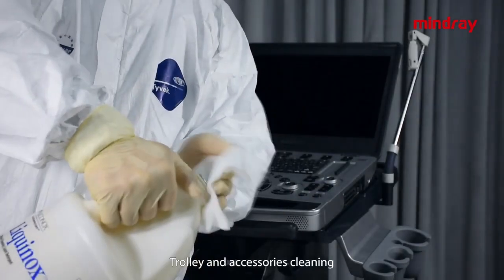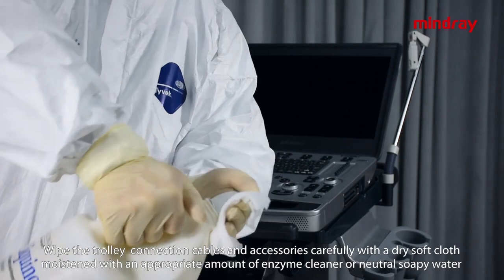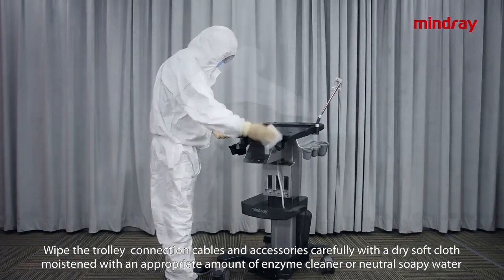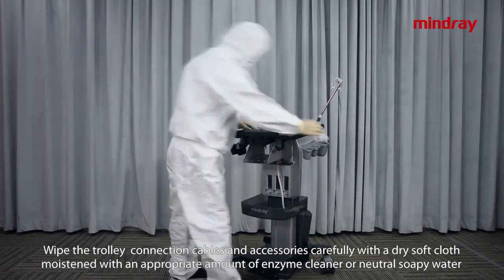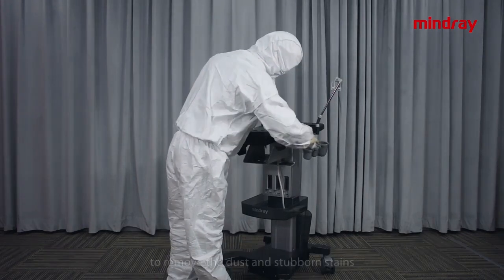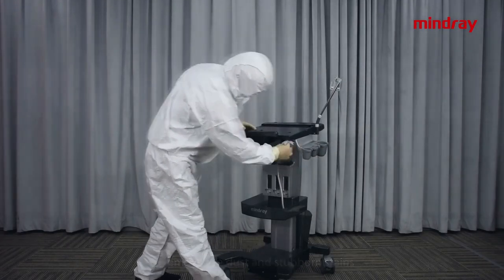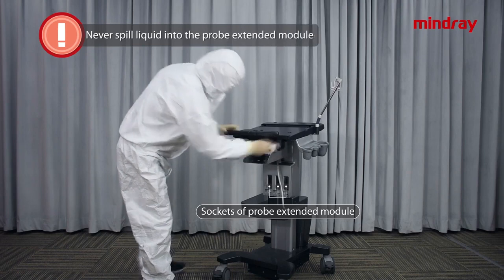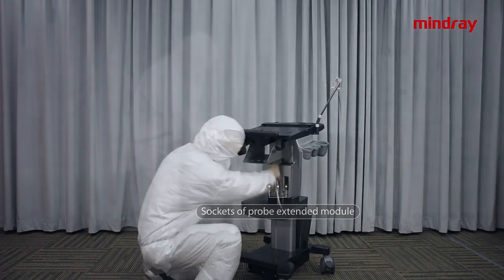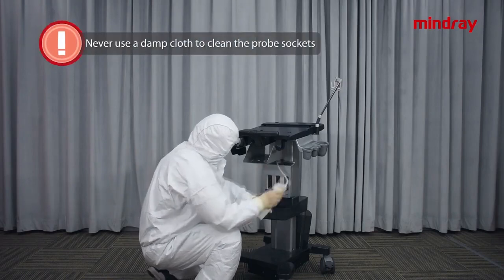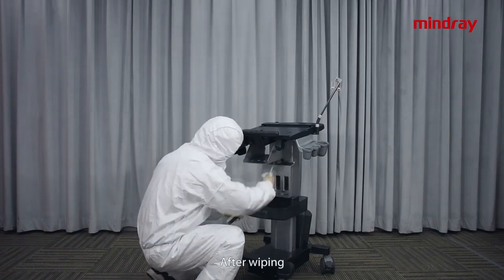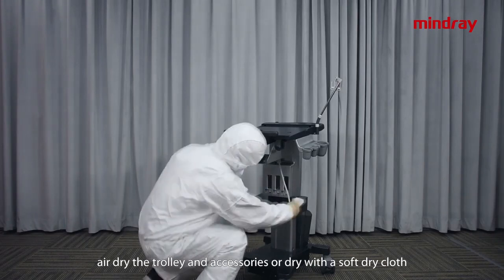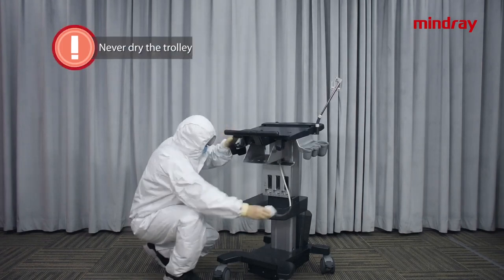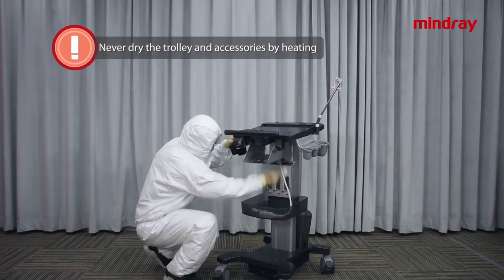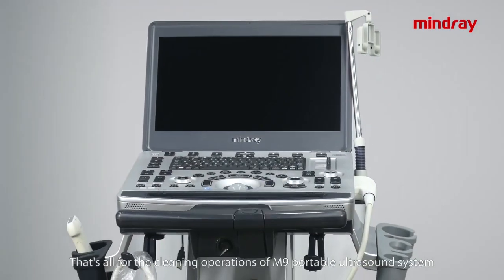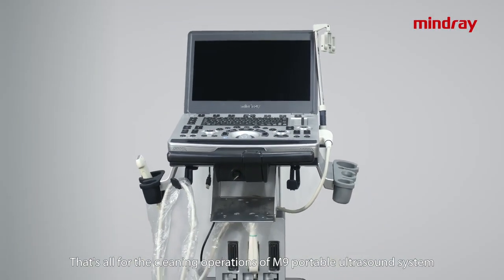Trolley and accessories cleaning. Wipe the trolley, connection cable, and accessory carefully with a soft dry cloth moistened with an appropriate amount of enzyme cleaner or neutral soapy water to remove the dust and the stubborn stains. Caution: never spill liquid into the probe extended module. Never use a damp cloth to clean the probe sockets. After wiping, air dry the trolley and accessories or dry with a soft dry cloth. Never dry the trolley and accessories by heating. That's all for cleaning operations of M9 portable ultrasound system.